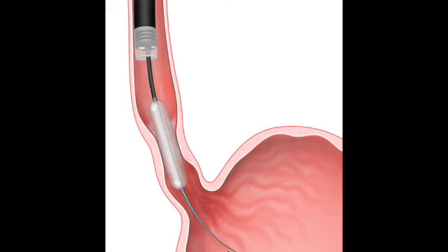That makes the next step in the prep phase make total sense. Because once the assistant has drawn those 35 cc's of water, they point the gun straight up and pump the handle to expel any residual air from the syringe. Yeah, they cannot afford even a single bubble of air. Right, because it would compromise that incompressible fluid dynamic. But then the source highlights a step that seems entirely counterintuitive to me at first glance. The vacuum step. Yes, before handing the balloon over to the doctor, the assistant attaches it to the gun, points it downward, switches to the deflation position, and pumps the handle until it physically bottoms out. They pull this massive negative pressure vacuum on the balloon to ensure it is completely, totally collapsed.